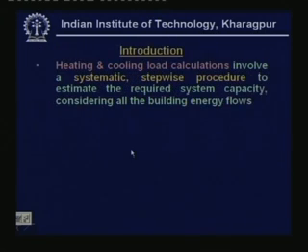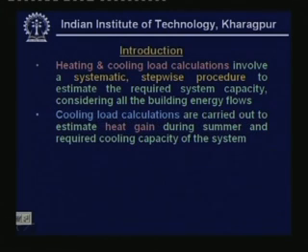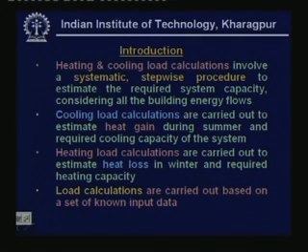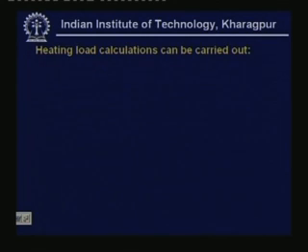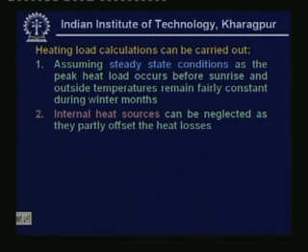Heating and cooling load calculations involve a systematic stepwise procedure to estimate the required system capacity considering all the building energy flows. Cooling load calculations are carried out to estimate heat gain during summer and find out the required cooling capacity, whereas heating load calculations estimate heat loss in winter and find the required heating capacity. Heating load calculations can be carried out assuming steady state conditions as the peak heat load occurs before sunrise and outside temperatures remain fairly constant during winter months. Internal heat sources can be neglected in heating loads because they partly offset heat losses.